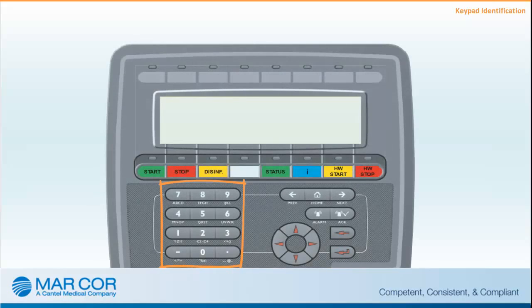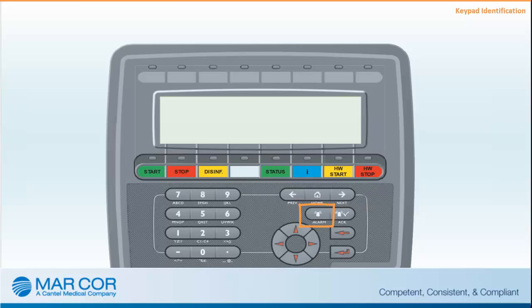The Number buttons, or keypad, permit entering codes and parameters during programming. The Home button returns the operator to the main CWP menu. The Previous and Next arrow buttons allow navigation back and forth through screen displays. The Alarm button lists current and past alarms. The Alarm Acknowledgement button resets alarms. The Arrow buttons move the cursor on the display. The Clear button erases unwanted data during programming, similar to the Backspace key on a computer keyboard. The Enter button confirms entered information and is used to perform commands; it will display setting ranges if pressed without first entering a value.